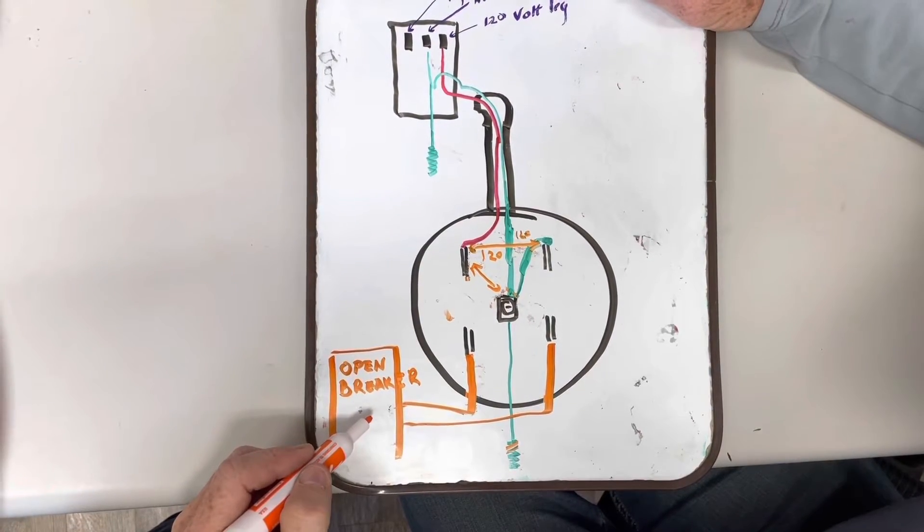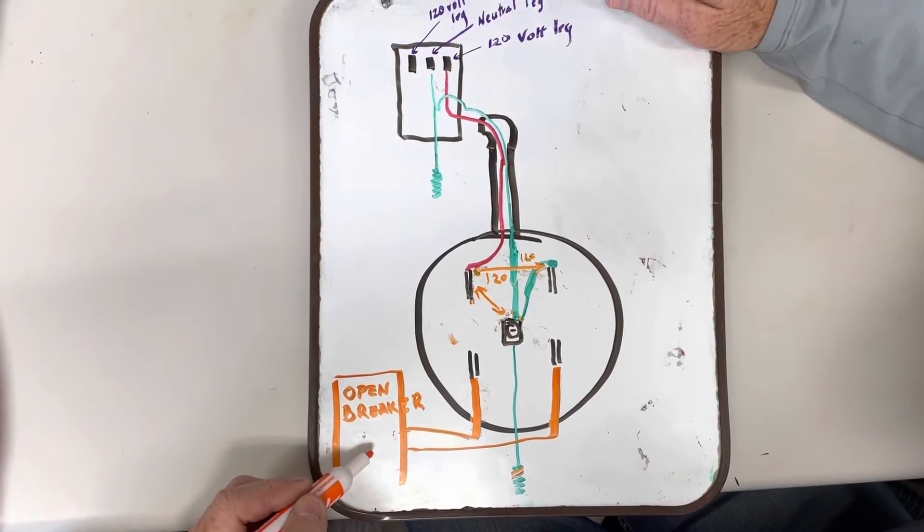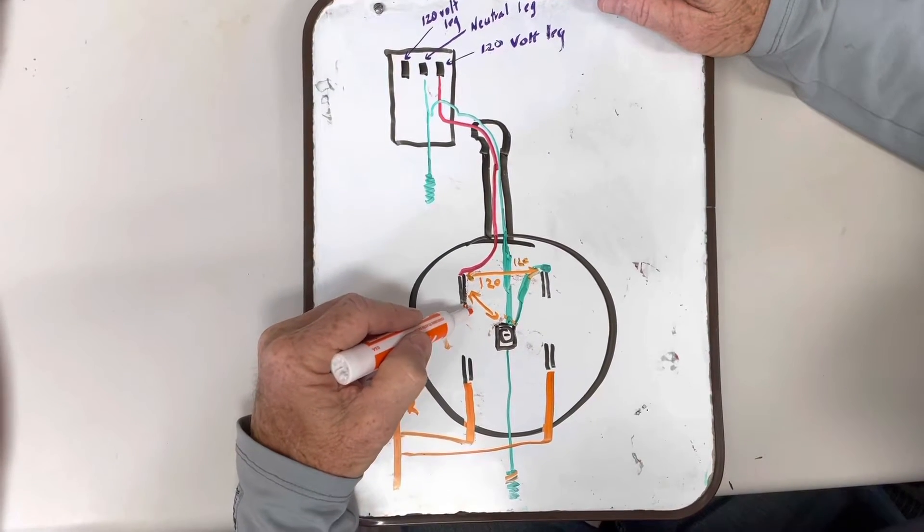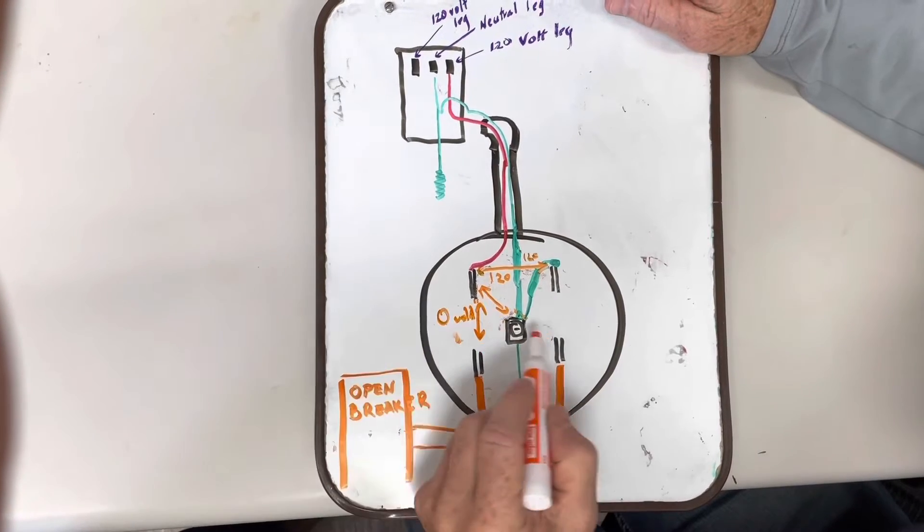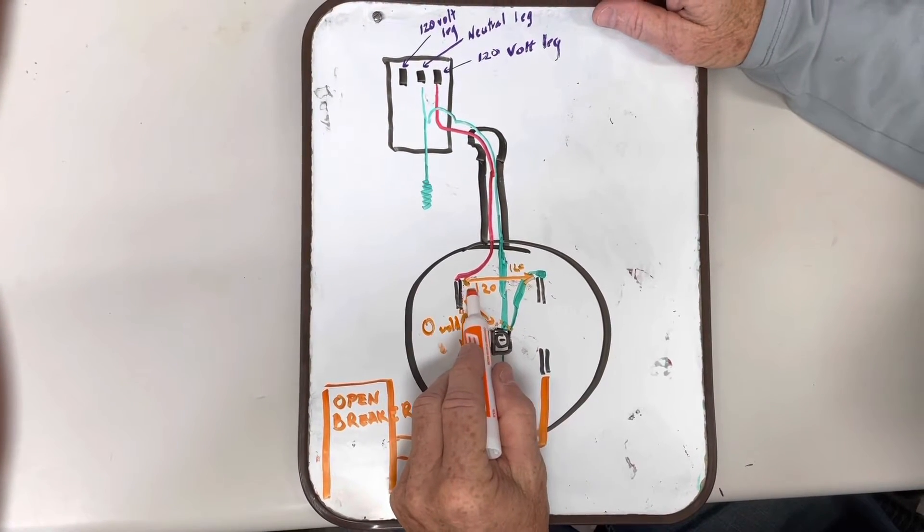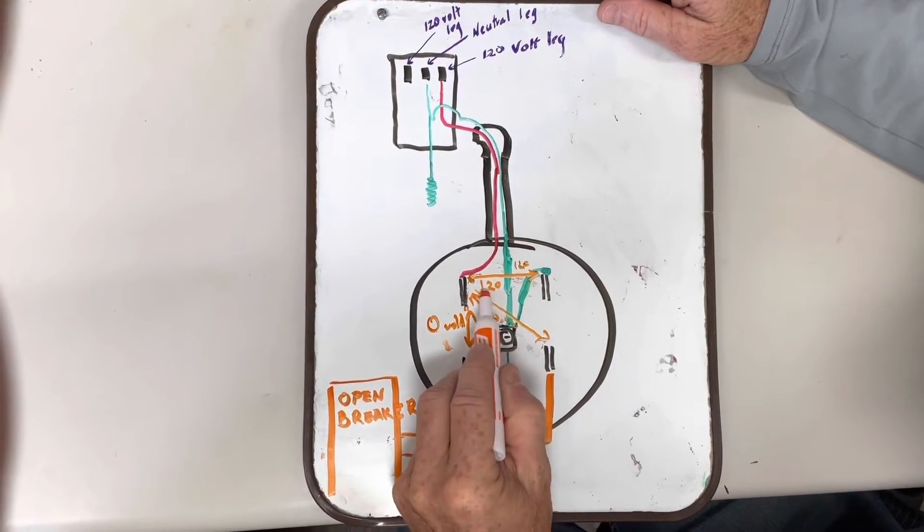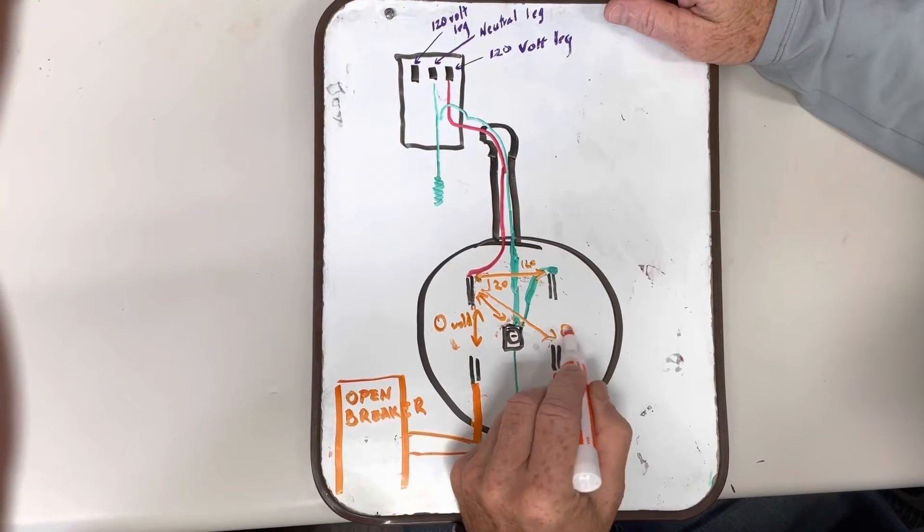With the breaker being open, we're doing all these checks. So I forgot to mention that, but from here to here, we're going to get zero volts. And from the hot lug here, all the way to this lug, we should get zero volts.